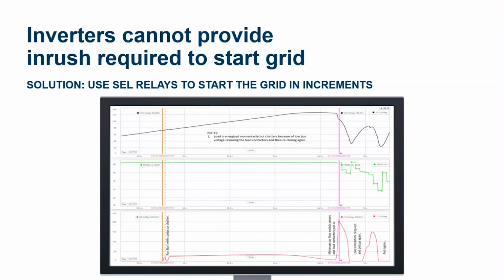So what this says is that you need to use relays to open breakers, to open contactors, to open building service entrances, to basically add loads in small increments so that you don't overload your inverters. It can be done, and it can be done very simply with just 1 or 2 equations in a relay. And that's a lot simpler and more reliable than an expensive microgrid controller.